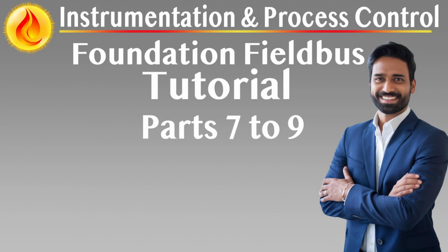VFDs facilitate plug-and-play replacement of field devices. When a new device is detected, the host can compare the new VFD's structure to that of the replaced unit, verify compatibility, and download saved configuration files. If the VFD profile and block arrangement match, the device can be reintegrated without manual reprogramming. This functionality significantly reduces downtime during maintenance and supports standardization across large facilities.